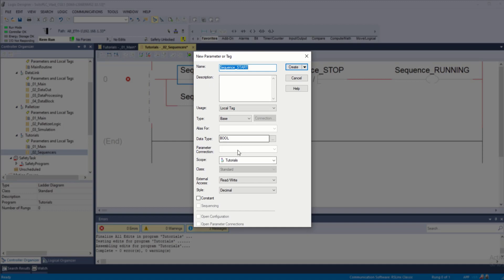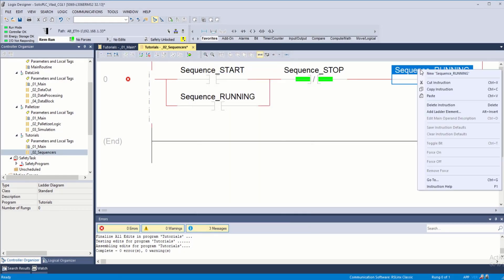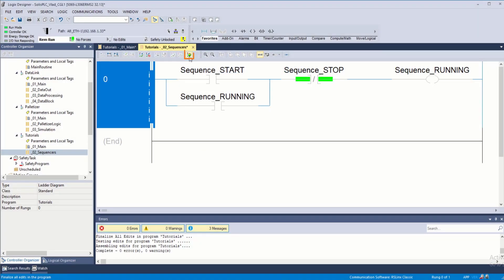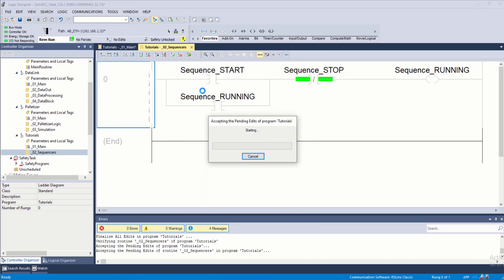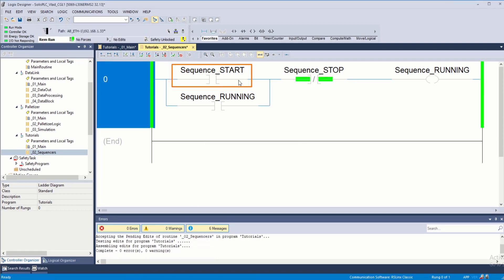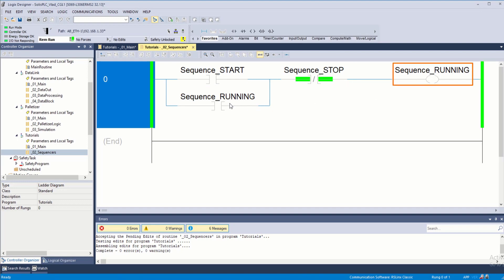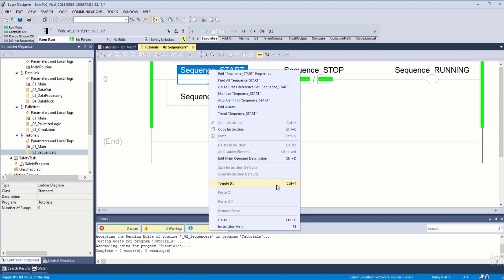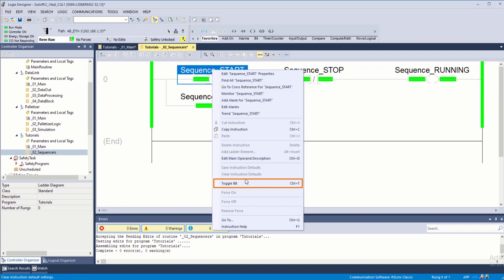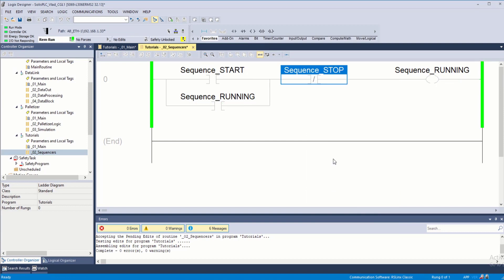I'm going to copy sequence running underneath and change the OTE to an XIC instruction. Right-click, new — sequence start, sequence stop, sequence running are all going to be booleans underneath tutorials. Click create. To demonstrate: something is going to start our sequence, something is going to stop the sequence, and once it is running it keeps track of the condition. I can right-click and toggle bit — the sequence is now running. We can release this button and it remains running until stopped.